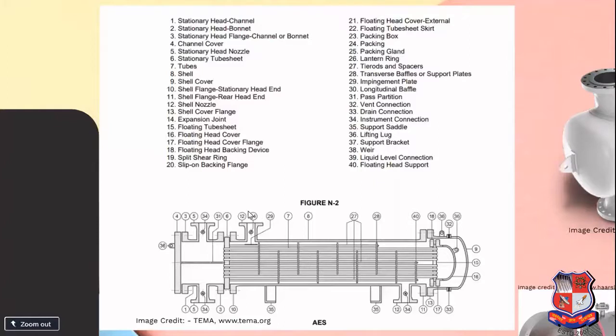Similarly, for the shell side fluid, this is a nozzle for the entry of the shell side fluid, and this is the exit of the shell side. On each nozzle you will have a connection point. Those connection points can be useful for temperature measuring devices or pressure measuring devices. And the fluid entering from this side will pass through the tubes, and here it will take a second pass through the tube, and in this way it will exit.